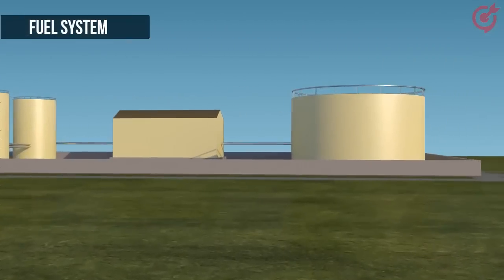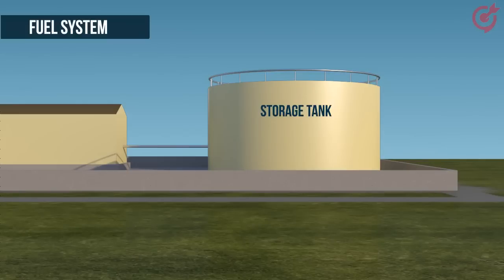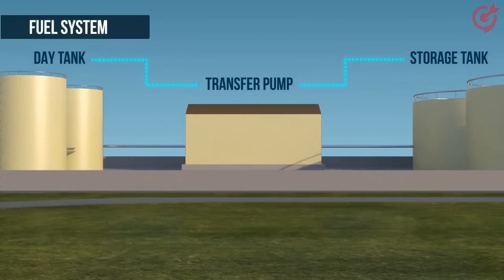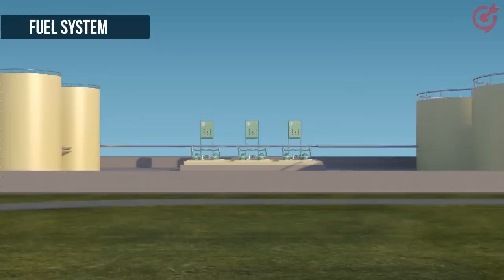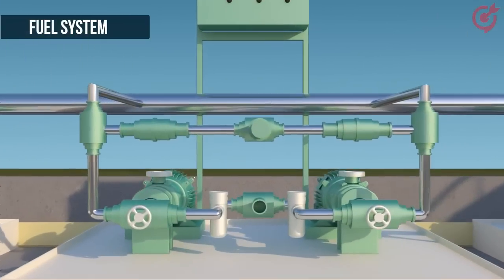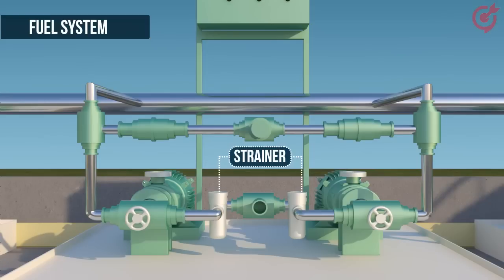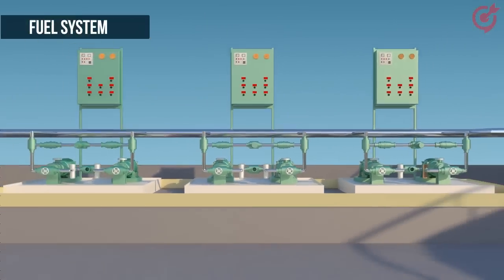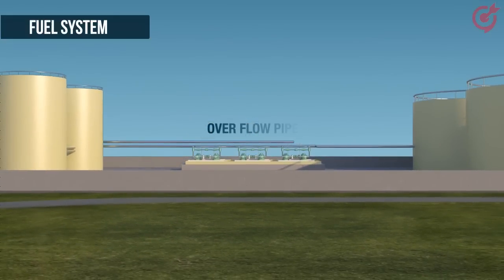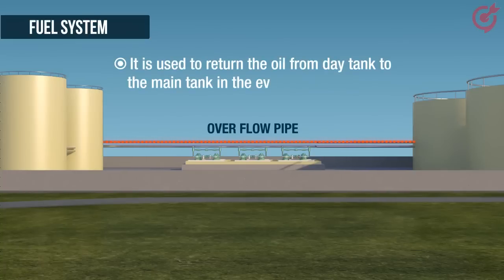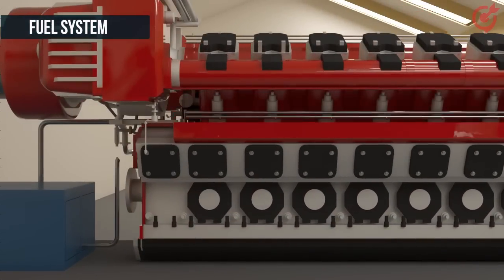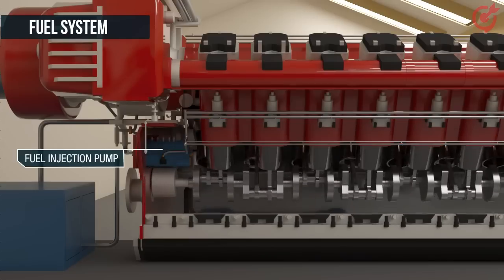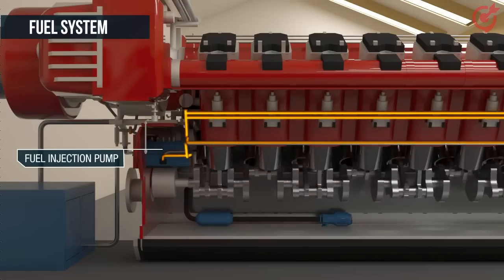The fuel system consists of a storage tank, or main tank, to store the fuel. The oil is pumped into the day tank via a transfer pump. During the transfer, oil passes through strainers or filters to remove solid impurities. An overflow pipe connects the day tank to the main tank, returning oil from the day tank to the main tank in the event of overflow. The fuel injection pump injects fuel from the day tank into the engine cylinder at a high pressure of about 100 bars.